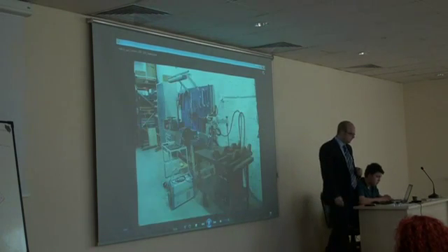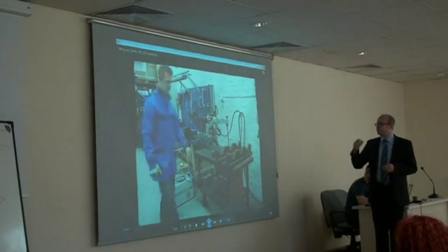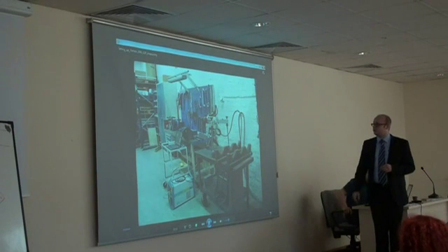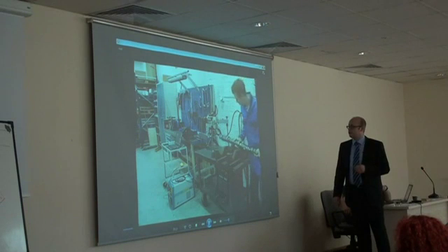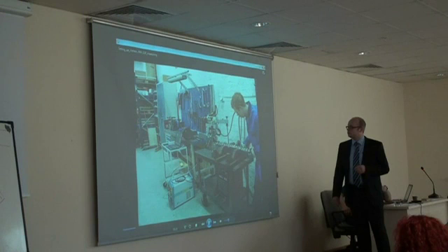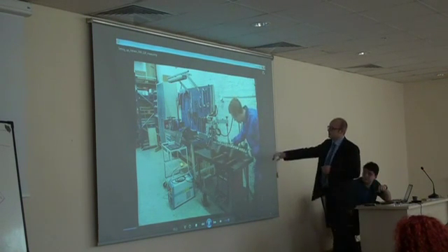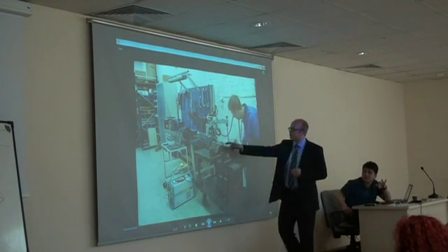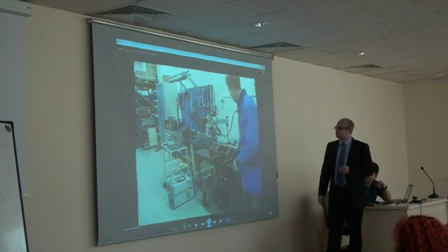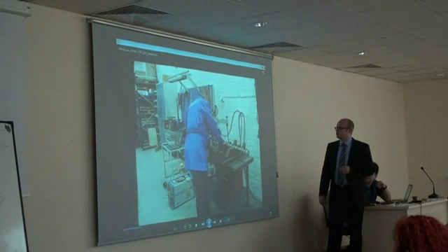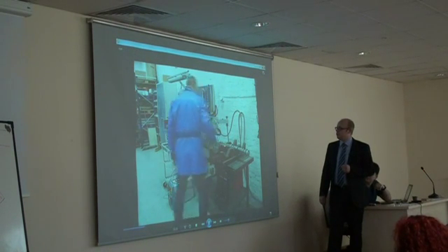And you can see that this is a really portable unit. You can do measurements also on a soft floor or wherever you want. The guy has a camshaft and would like to make some measurements over there. So you can see he puts the cam lobe under the collimator.